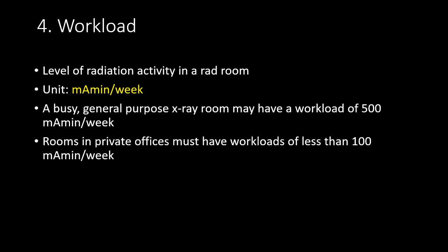The workload refers to the level of radiation activity in a room. So you would calculate for the physicist specifically the mA times minutes per week that you would expect to have. A busy general purpose X-ray room may have a workload of 500 mA times minutes per week, whereas rooms in a private office may have workloads of less than 100 mA times minutes per week.